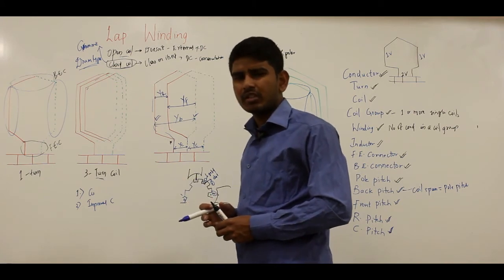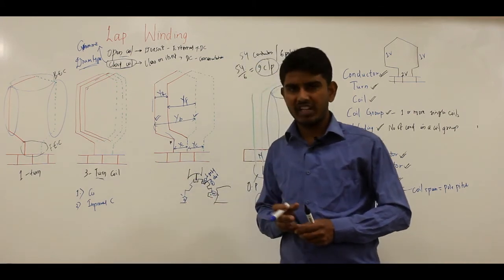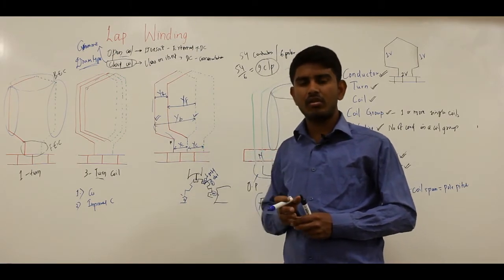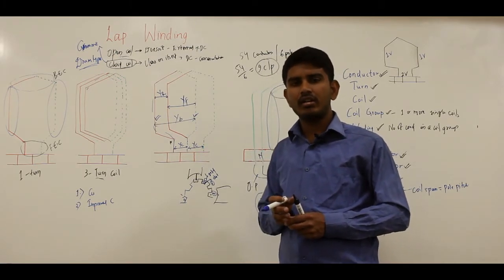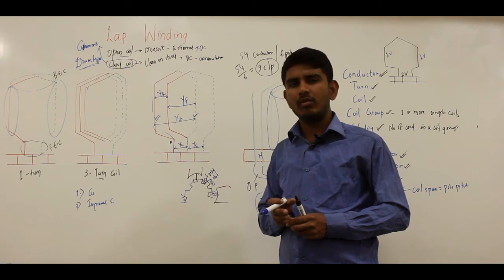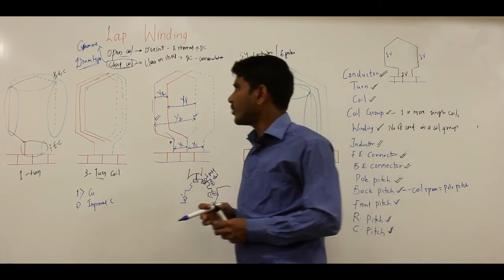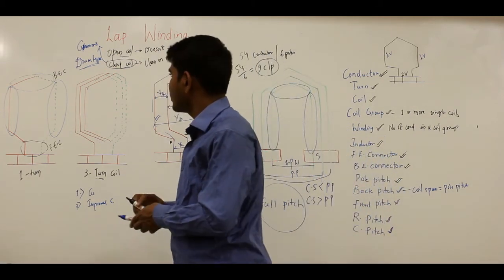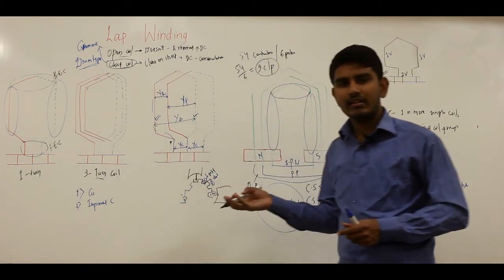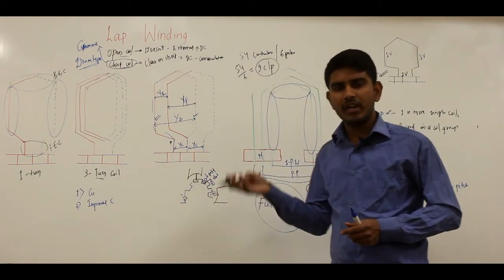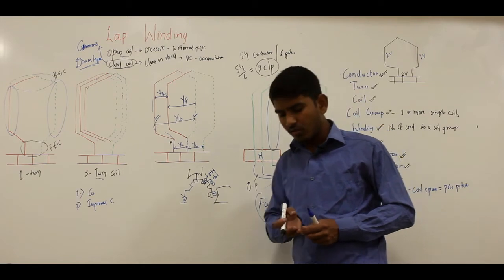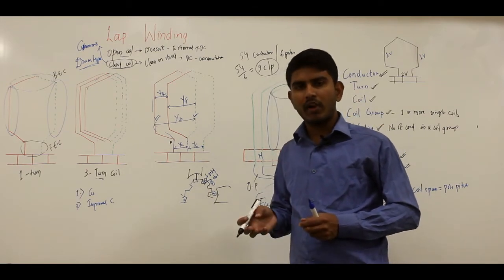The drum type winding can be single layer or double layer. Mostly double layer is used where coils can be preformed and insulated before placing in the slots. Due to economic reasons double layer winding is preferred. These drum type windings are basically of three types: lap winding, wave winding, and frog-leg winding, which is a combination of lap and wave winding.